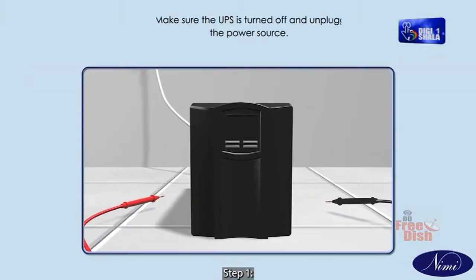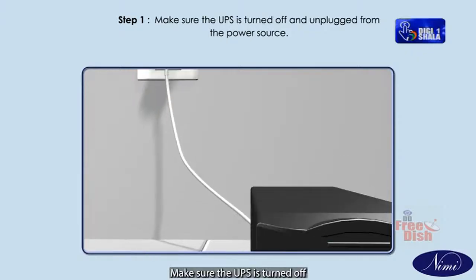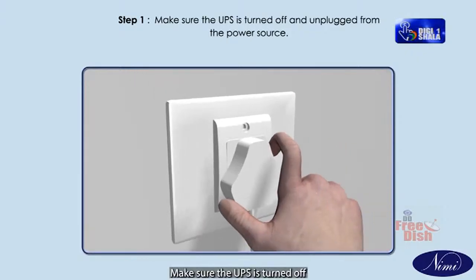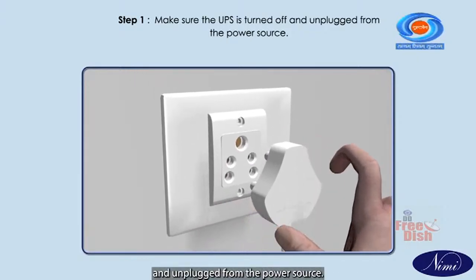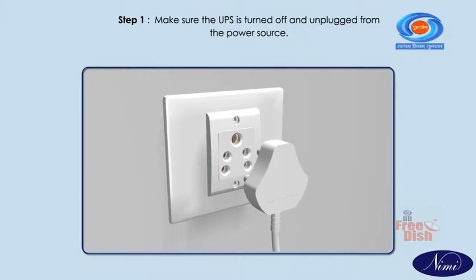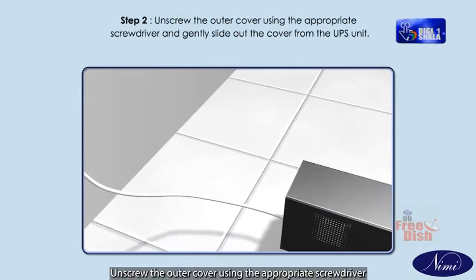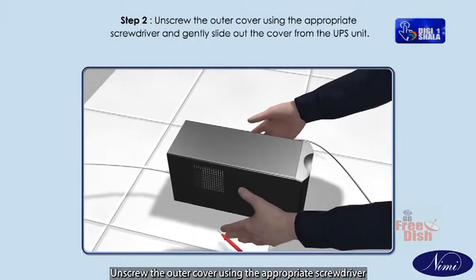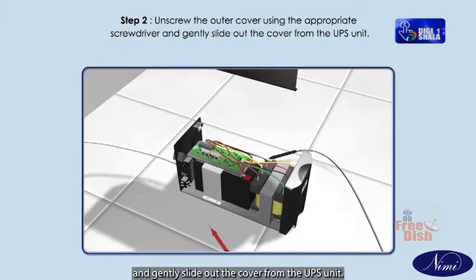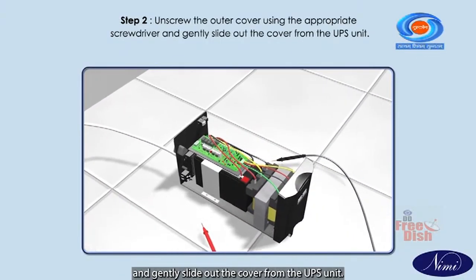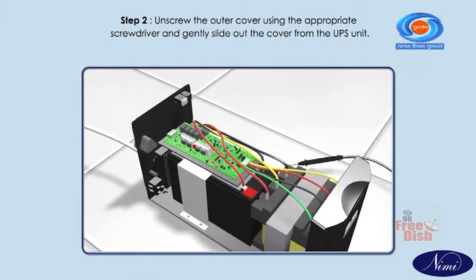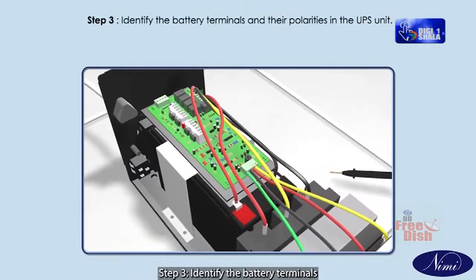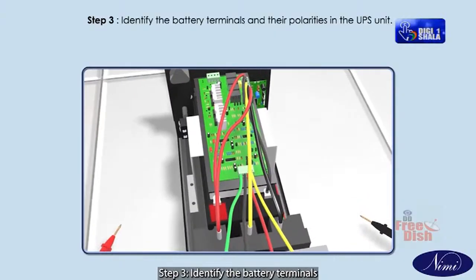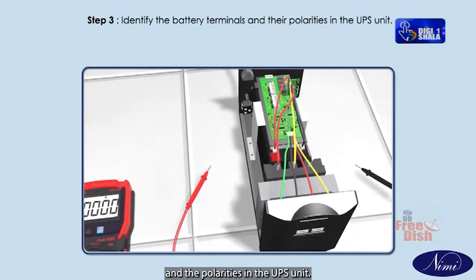Procedure. Step 1. Make sure the UPS is turned off and unplugged from the power source. Step 2. Unscrew the outer cover using the appropriate screwdriver and gently slide out the cover from the UPS unit. Step 3. Identify the battery terminals and their polarities in the UPS unit.